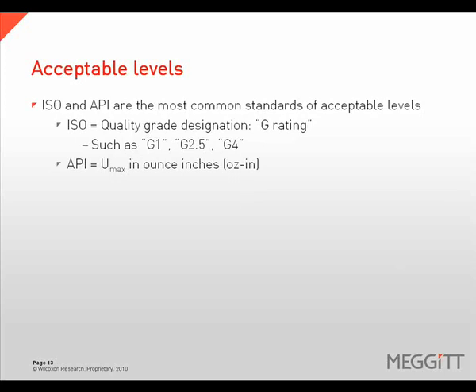To determine acceptable levels of unbalance, there are two standards commonly used: the ISO and API standards. ISO assigns a G rating based on the amount of residual imbalance. The API standard designates the remaining unbalance as Umax, expressed in ounce inches.